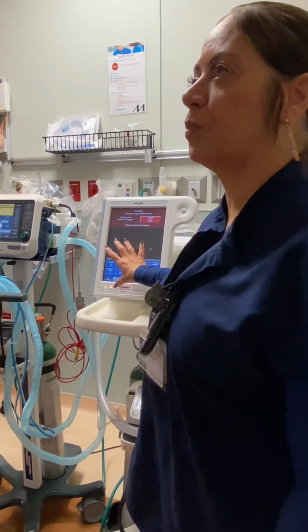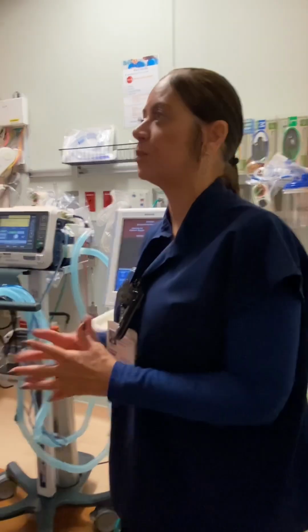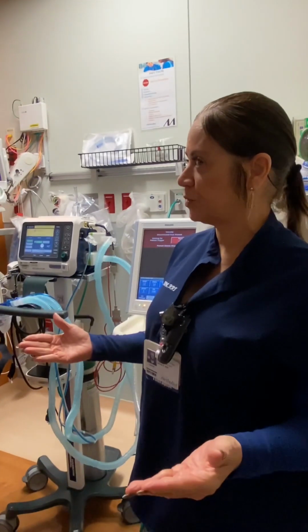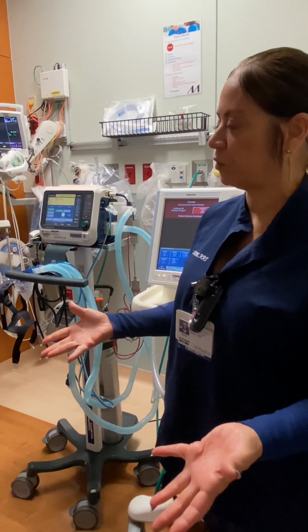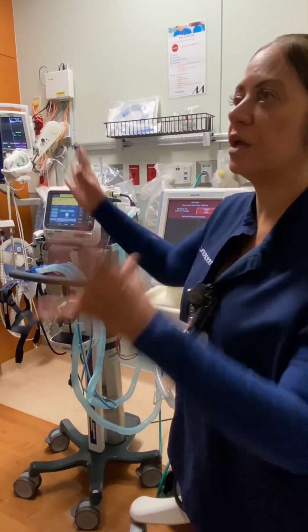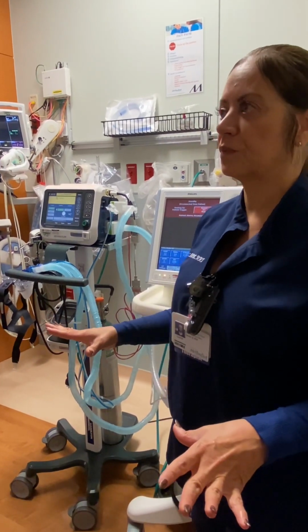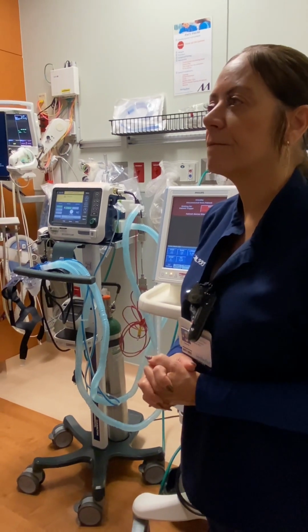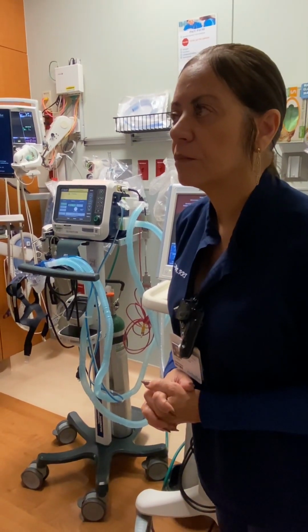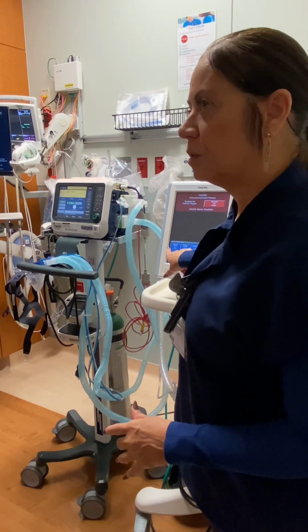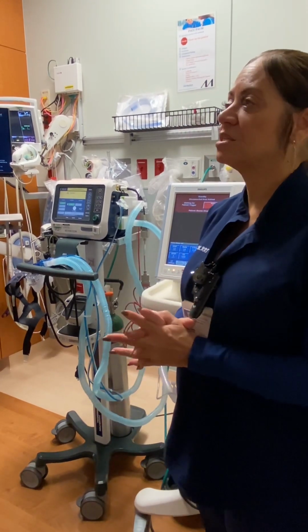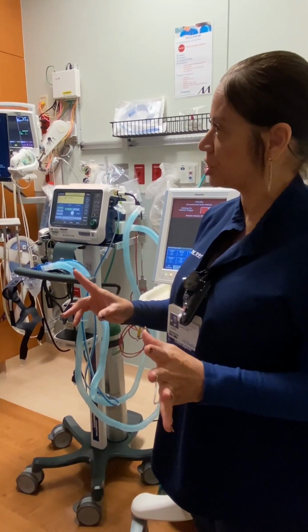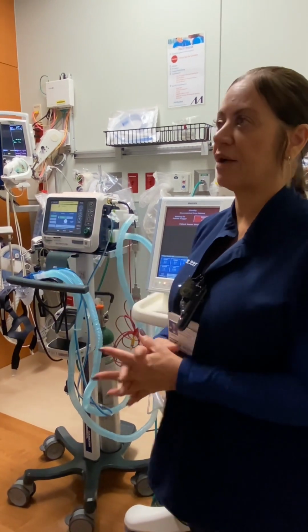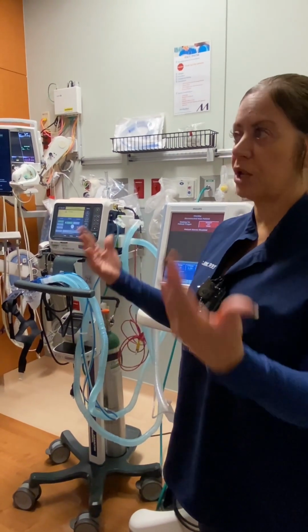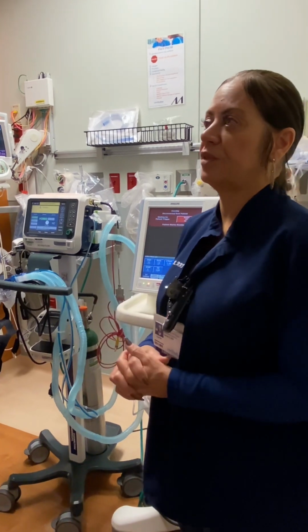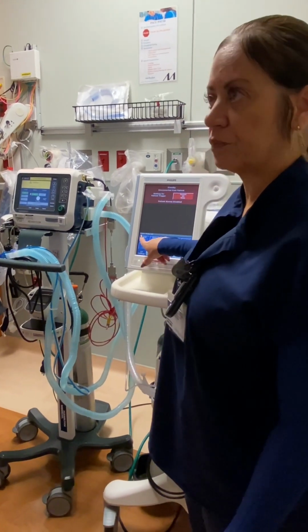So this is the mode you would put on someone who comes out groggy, or we find out he's COPD, correct? And we think his CO2 is high. I know you've heard that back here before. This is the mode we would do. The other mode, oxygenation only. What's the usual IPAP pressure for the standard? Yeah, the standard. Anywhere from 10 to maybe 14 or 16, depending on the patient. We would have to look at the size of the patient, his blood gases. Suppose you have a CO2 in the 80s, you would go up on this number to blow that off.